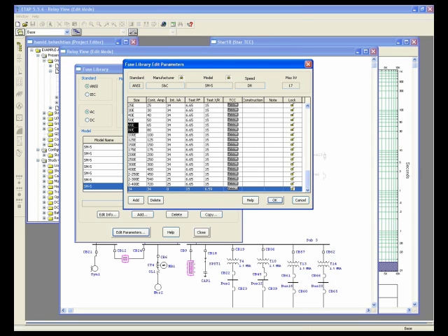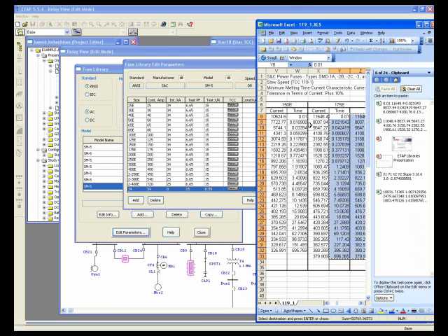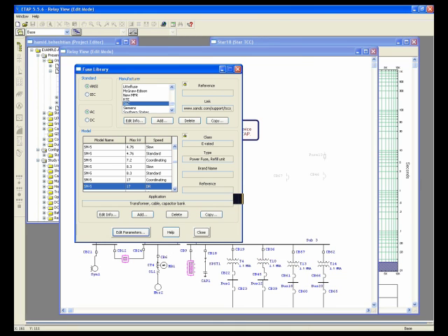Sometimes manufacturers do not publish all the sizes. So if you look at the manufacturer TCC, they may have, for example, size 40, size 50, 65, but they don't publish size 45 in between. So if you have that size and if you want to model that, one way is to extrapolate the curve. So if you have that Excel points, you can play with the numbers, so you can create additional curves for you.